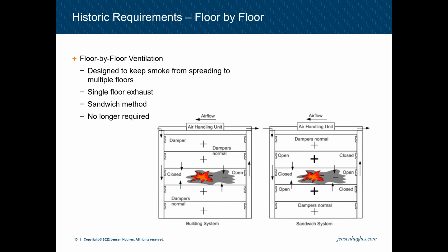A historic system that's not required anymore is a floor-by-floor ventilation system. These were required up until the 5th edition of 780 CMR, and these were designed to keep smoke from spreading to multiple floors, to keep it located on one central floor. There were 2 ways to design these systems. There's a single floor exhaust, shown on the picture's left side, and then we had what was called the sandwich method, which is on the right side.